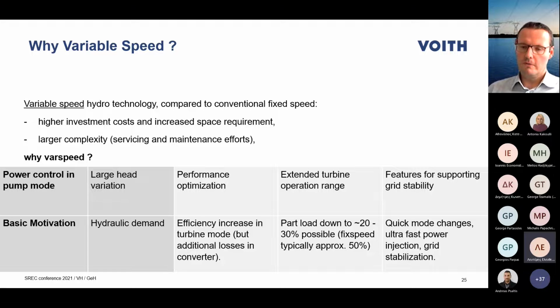But why is variable speed typically used? The basic motivation is to control also the pump power. It means that you don't have only the possibility to have on-off in pumping mode, but you also have the possibility to control the pumping input power in a certain range. There are several other needs for variable speed, but they are not so dramatic as the pump input power variation. For instance, a large head variation in the reservoirs could also require a certain speed variation to have a stable unit and stable operation.